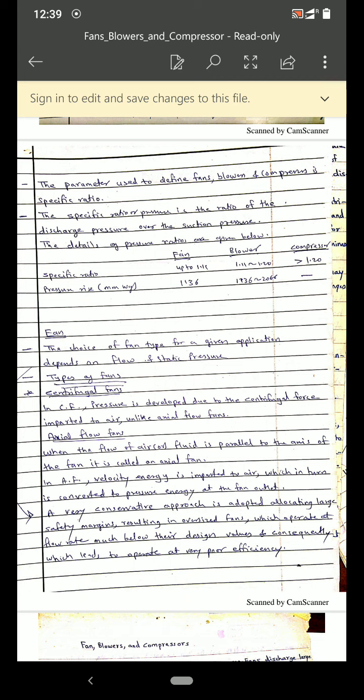It is differentiated depending upon the discharge pressure delivered by fan, blower and compressor, and specific speed. The discharge pressure delivered by fan is 0.04 atmosphere, by blower is up to 2 atmosphere, and by compressor is from 2 atmosphere to several thousand atmosphere. The specific ratio — that is discharge pressure upon suction pressure — for a fan is up to 1.11, and for a blower is between 1.11 to 1.20.